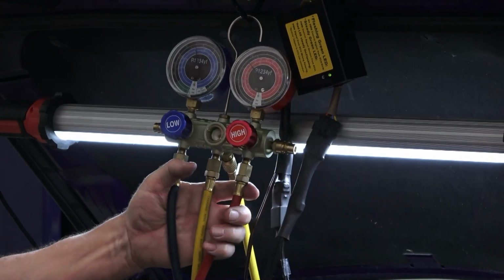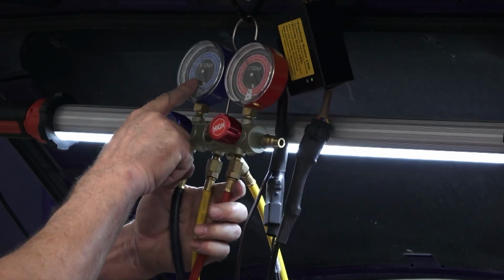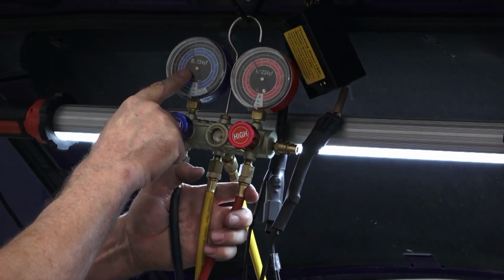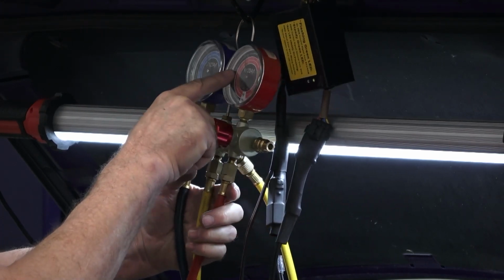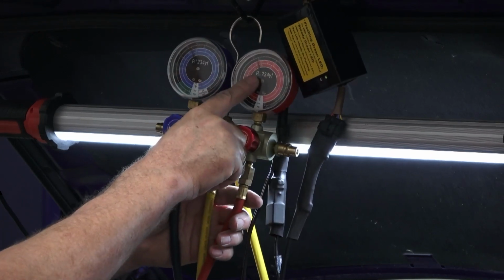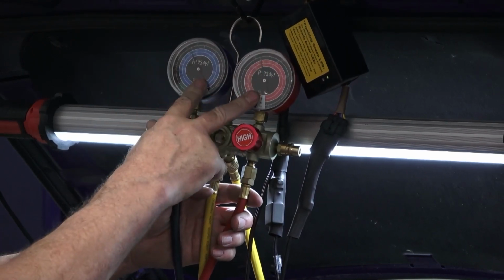If I look over here at my pressures, you can see low side pressure is starting to come down a little bit. High side pressure is just around 200 psi, and that's because the fans have not come on yet.